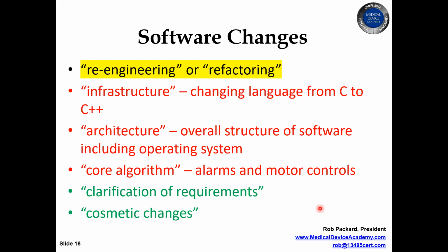Because often they like to see full revalidation of software when you make a change, but oftentimes if you're making minor modifications, you can explain these are the inputs, these are the outputs, and these are the only pieces that really need to be retested.